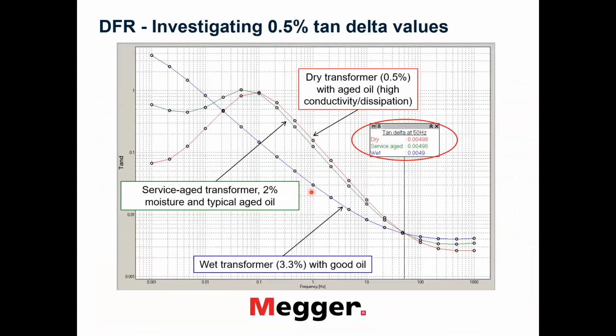So this is a Megger way of measuring or assessing the moisture content in transformers. And in this slide, I just would like to show what could be the advantages of using dielectric frequency response instead of, let's say, power factor measurement at 50 hertz of power frequency.